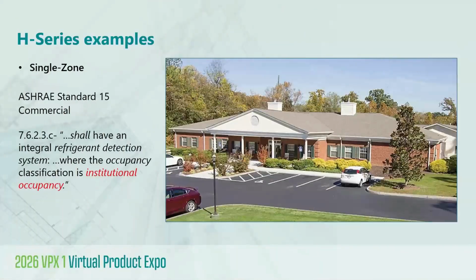So let's shift now and talk about a commercial application for single-zone H-Series systems. In this example, let's just say it's an assisted living facility. By ASHRAE definition, where occupants cannot readily leave the premise or a portion of the premise without the assistance of others, in this example, it would be considered what they call an institutional occupancy. So the point to make here is, regardless of the maximum allowable refrigerant charge, now it's worded a little bit differently in standard 15, it's known as effective dispersal volume charge, or EDVC, that in institutional occupancies LDS is always going to be required, period.